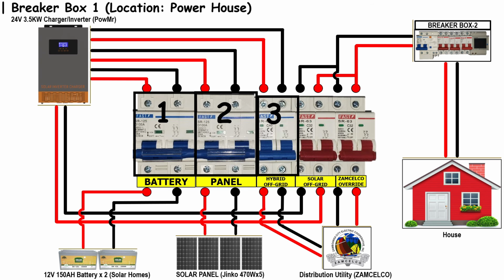I'm still going to observe if my two batteries can last for 8 hours of autonomy. At number 4, I have a 32 ampere manual transfer switch with mechanical interlock. This means the guys at home can choose between off-grid, hybrid off-grid, or on-grid. This is very helpful in case there's a fault and I'm not around. Cool, right? So there you go.